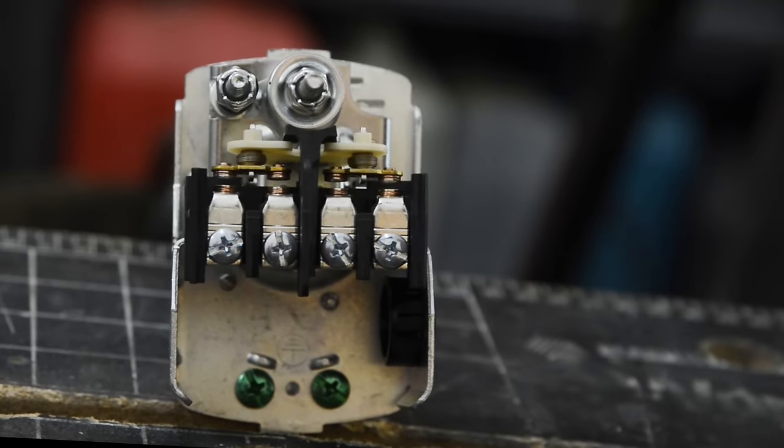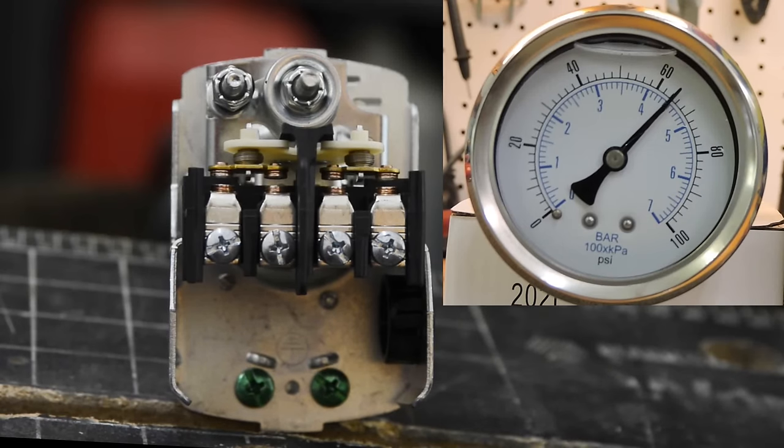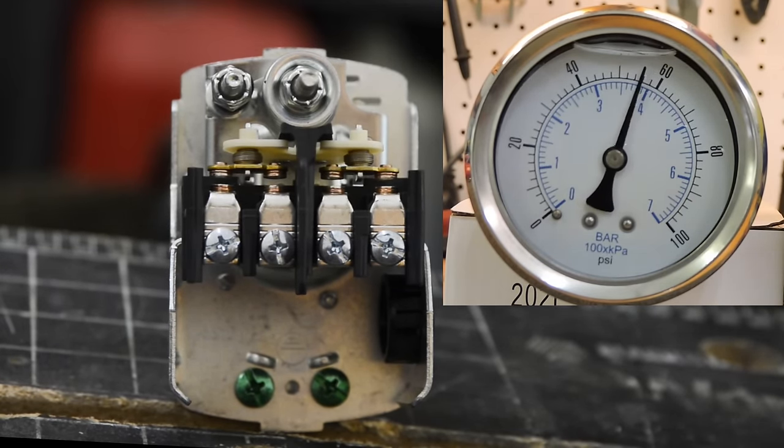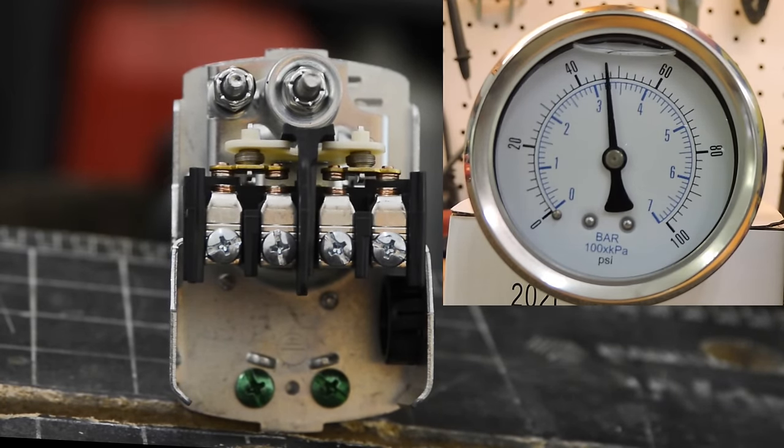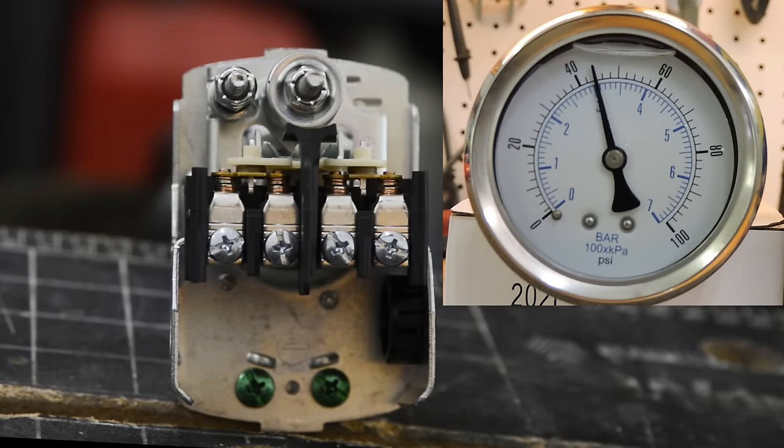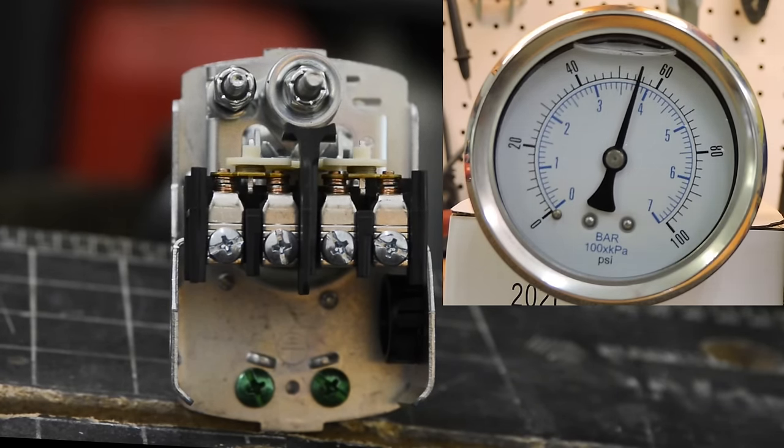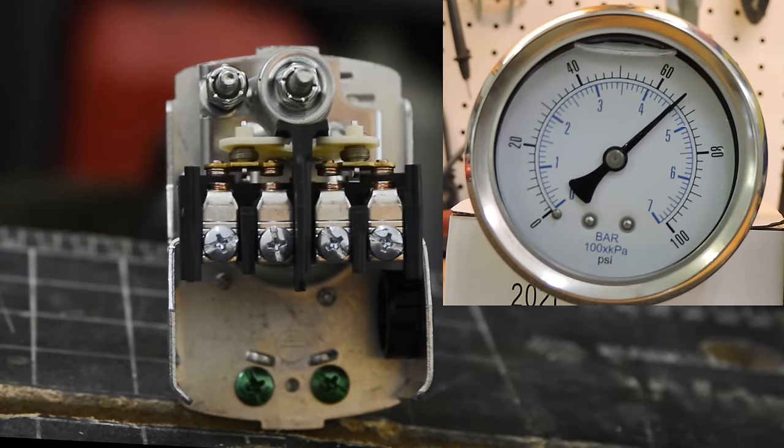We're going to show you the contacts opening. The contacts are open now because the pump will be turned off. The pressure has been satisfied. So as we lose pressure, the contacts will close. And now the pump is running until the pressure is satisfied again. So while the pump is running, the pressure is increasing until it reaches cutoff.